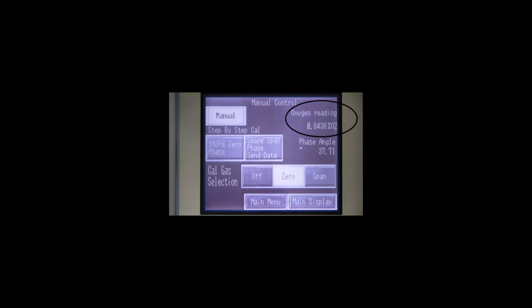As the zero gas begins to purge out the process gas, you can see the oxygen reading begin to drop very quickly. It really doesn't take very long to get the measurement all the way down to zero. Now, let's switch over to the span gas. The span gas that we're using today is 2% oxygen in nitrogen. Once again, the oxygen trends up very quickly. Eventually it comes in and stabilizes at 2% of the oxygen reading.